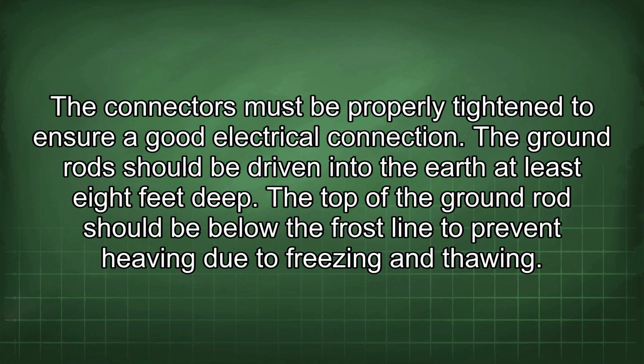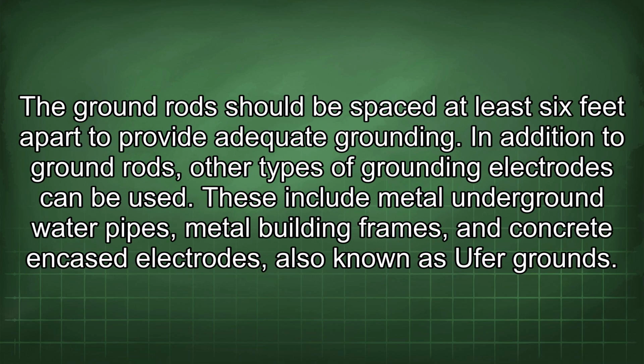The ground rod should be driven into the earth at least 8 feet deep. The top of the ground rod should be below the frost line to prevent heaving due to freezing and thawing. The ground rods should be spaced at least 6 feet apart to provide adequate grounding. In addition to ground rods, other types of grounding electrodes can be used. These include metal underground water pipes, metal building frames, and concrete encased electrodes, also known as Ufer grounds.